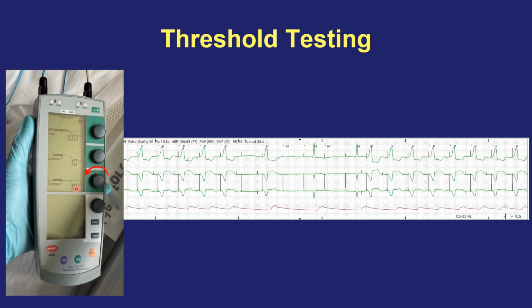And the number that is associated with capture, that's the lowest number, let's say 5 milliamps, is called the pacing threshold. You'll see day after day in the postoperative setting that that number will go up, because that metal electrode, that strand that is threaded through the myocardium, will get inflamed. There's local reaction in the myocardium to that metal, and that local inflammation will create a barrier to the transmission of electricity, and that pacing threshold will go up.